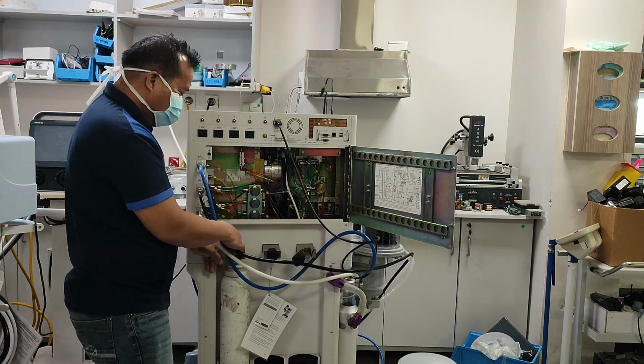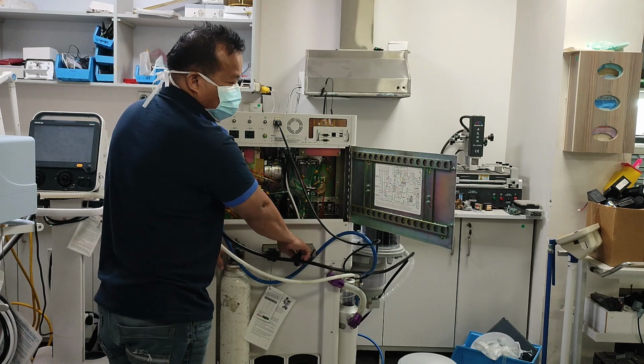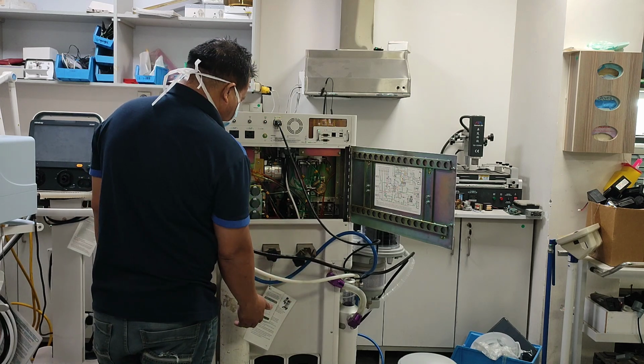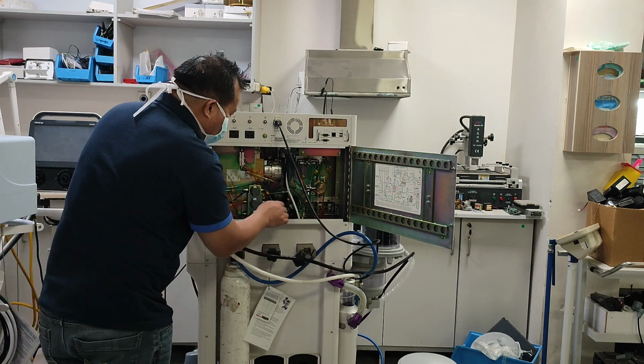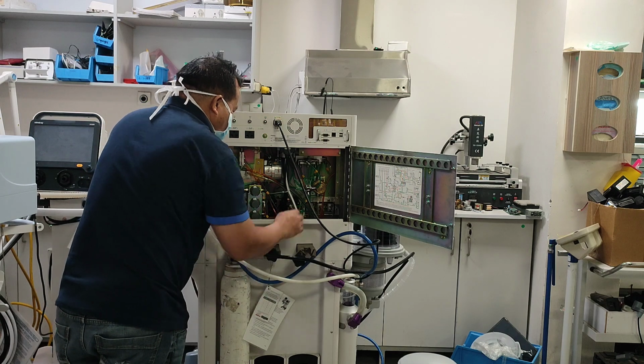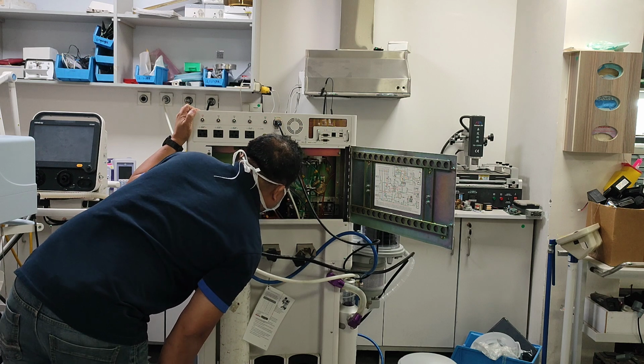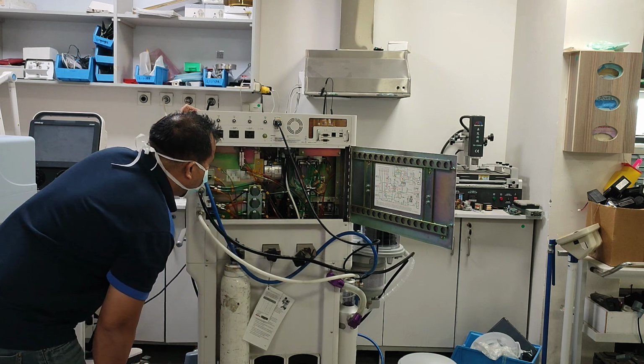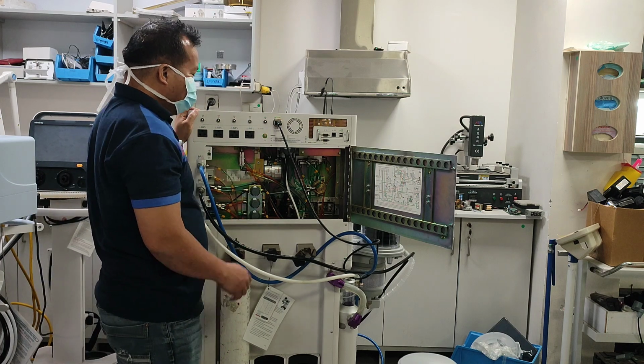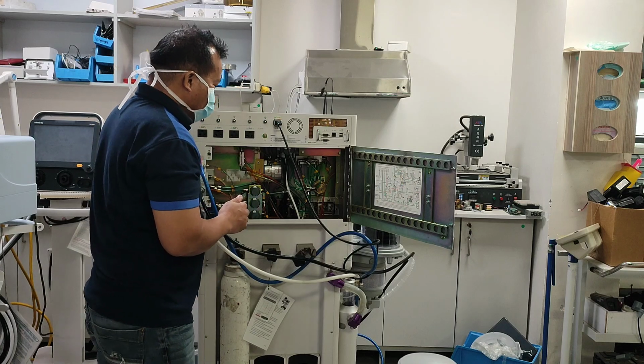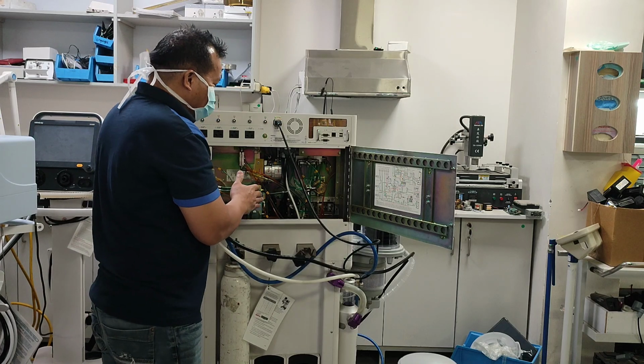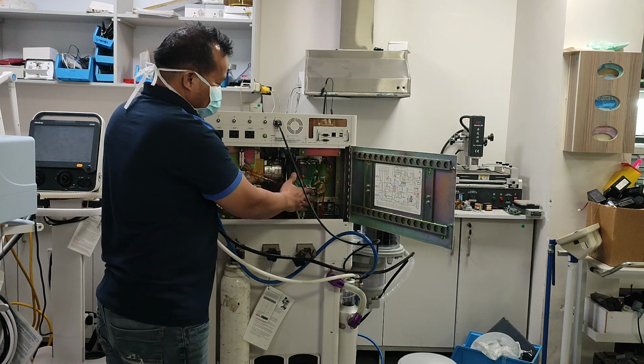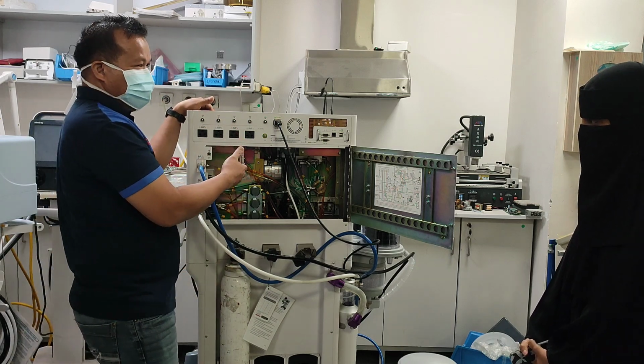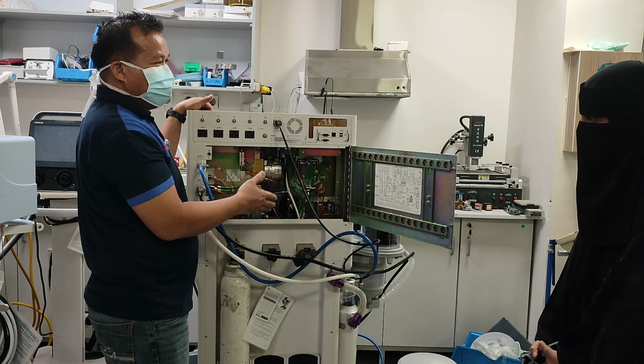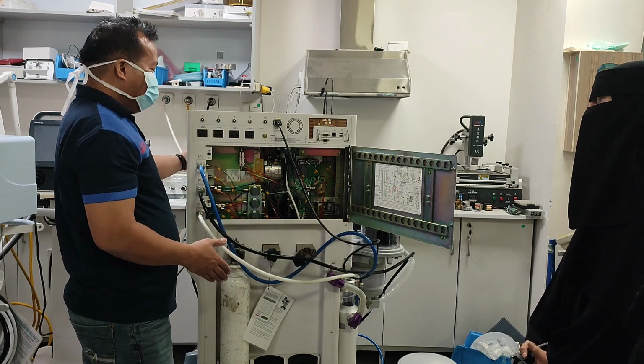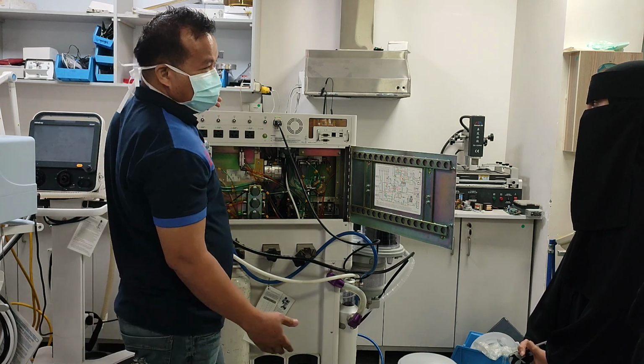So what else is here? If you see here, there is oxygen, air, and nitrous. There are 3 gases here for the cylinders. They are the same color as the hose, so you know which is air, which is oxygen, and which is nitrous. If you have an issue with a leak, you should also check this side. For example, if the machine does not pass the previous check, it will fail because the leakage is too big. You can check in the patient module, and also check this one here, by visual only, because we cannot do anything else for that.